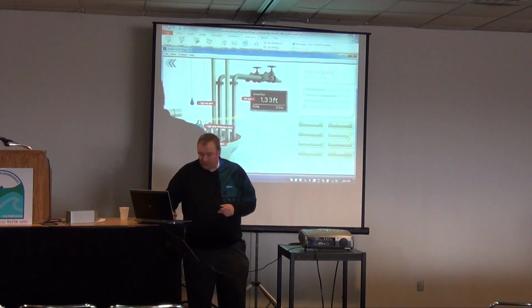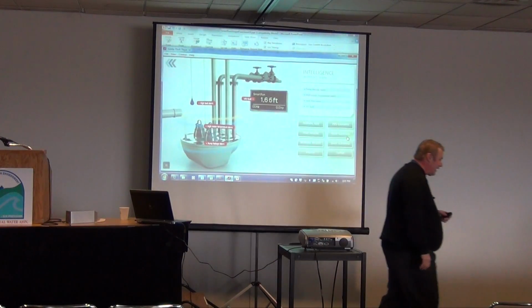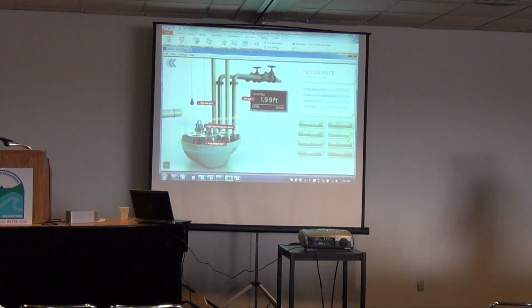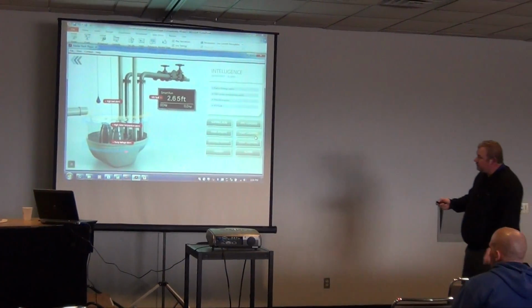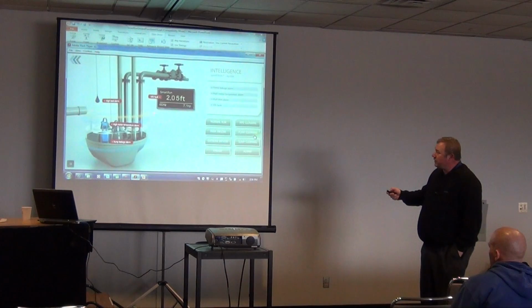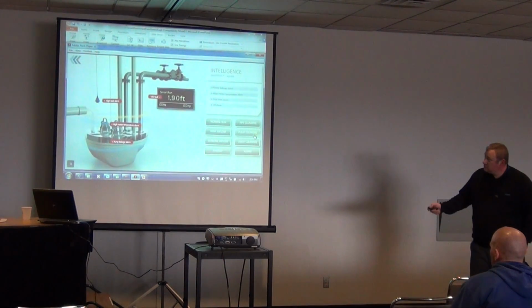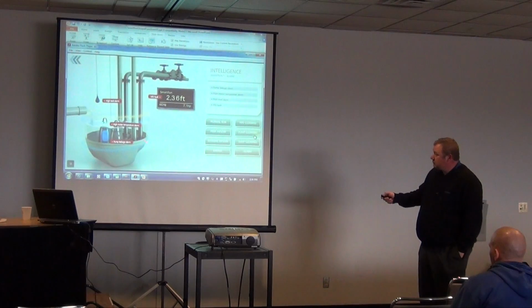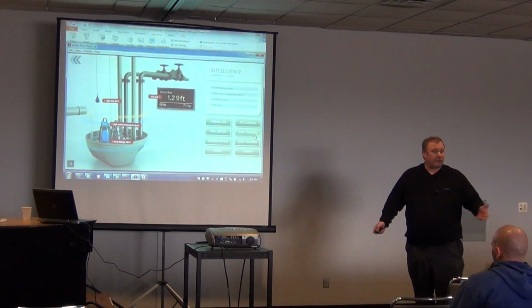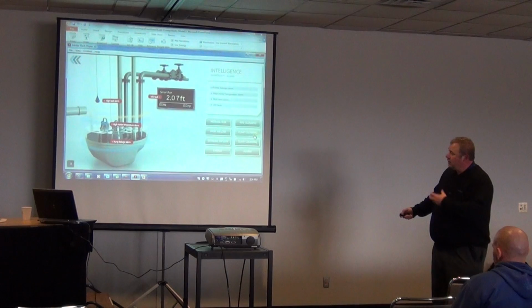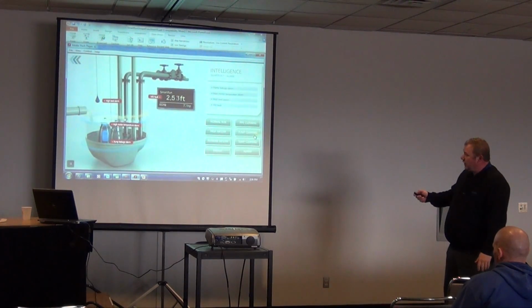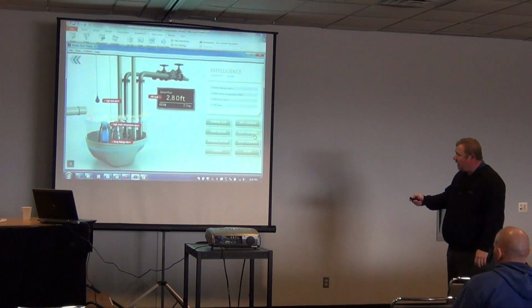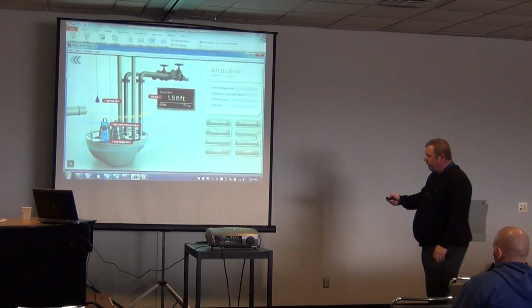I'm sure as operators you want to know about alarming capability. I said, as simple as it can be, just using those units alone, if we look at this here, these are the alarms that we can pull out of it right away. If you've got a simple duplex neighborhood type station out in your community, you want to save some energy on it, and you put those units in, we can get these alarms. The VFD fault, high level alarm, high motor temp and leakage, right here.